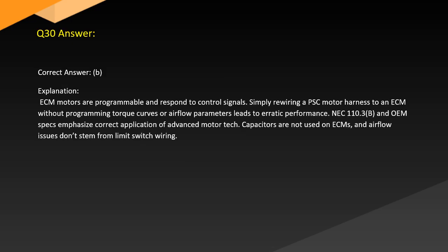Answer. Correct answer, B. Explanation. ECM motors are programmable and respond to control signals. Simply rewiring a PSC motor harness to an ECM without programming torque curves or airflow parameters leads to erratic performance. NEC 110.3(B) and OEM specs emphasize correct application of advanced motor technology. Capacitors are not used on ECMs, and airflow issues don't stem from limit switch wiring.